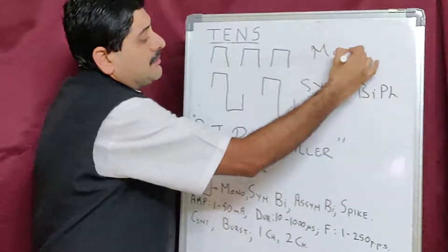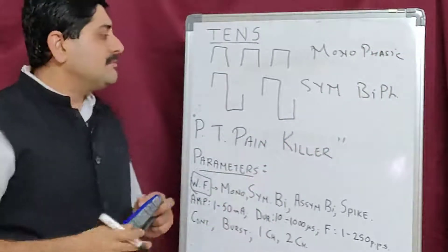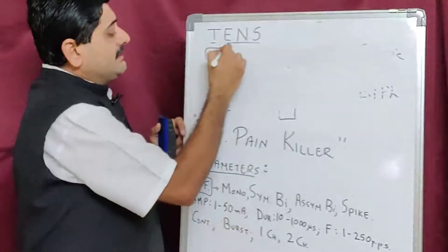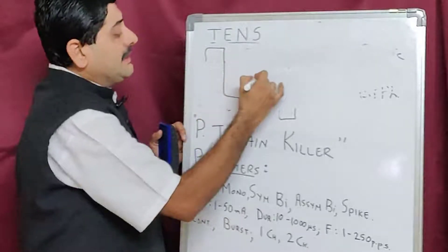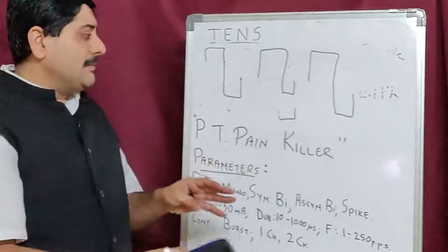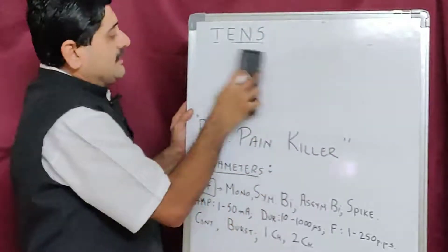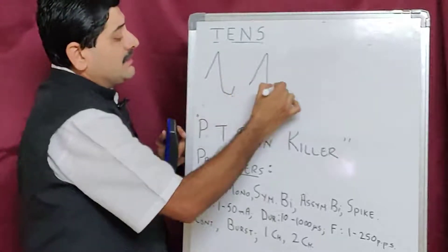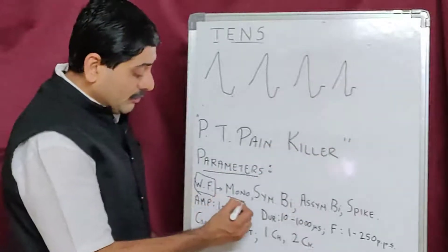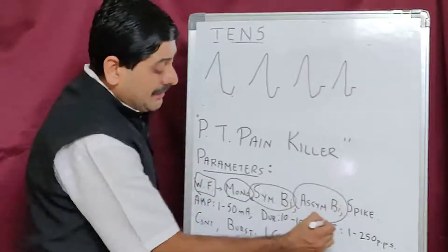Monophasic has a single phase, symmetrical biphasic has two equal phases. Then there is asymmetrical biphasic, where there is no symmetry between the upper and lower current. The last type is a twitch or spike current, where the current flows in a spike pattern. So there are four waveform types in total.